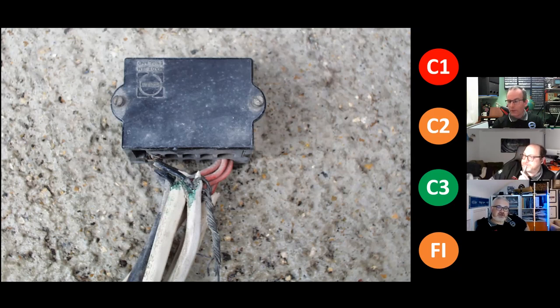I go with electrical connections, 526.1 on that. That's just not suitable or sufficient. I'd also go with good workmanship and proper materials, 134.1.1. It's just not good workmanship, nor the correct use of materials. So to me, that's a C2. I wouldn't want to improve that. I'd want to rip it out and say that's potentially dangerous. You need to rip that out.